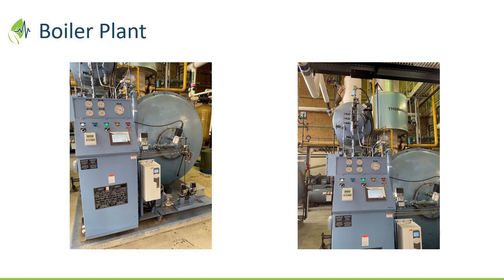That was a long time ago, because we didn't take that up for a long time. But to John's point, on traditional methodology with economizers, these days if you're a gas-only plant, most manufacturers will fix your economizer closed, so you're always utilizing heat. But when you had dual fuel applications and you put the boiler on oil, the damper would be fixed into that safety string and it would lock open. But if you're only pumping oil once a year, they start to bind. And that's why they're left. Because it's like, well, whatever, we're just doing it for oil anyway, it's not that important. Plus they're way up in the ceiling and you can't shut the plant down sometimes. So this is why it happens. It's no one's fault, it's just a byproduct. If we're aware, we tackle it.